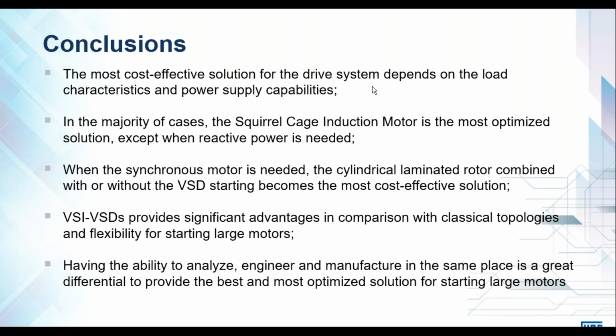Conclusions. The most cost-effective solution for the drive system depends on the load characteristics and power supply capabilities. In the majority of cases, the squirrel cage induction motor is the most optimized solution, except when reactive power is needed. When a synchronous motor is needed, the cylindrical laminated rotor, combined with or without VSD starting, becomes the most cost-effective solution. Voltage source inverter VSDs provide significant advantages in comparison with classical topologies and flexibility for starting large motors. Having the ability to analyze, engineer, and manufacture in the same place is a great differential to provide optimized solutions for large motors.